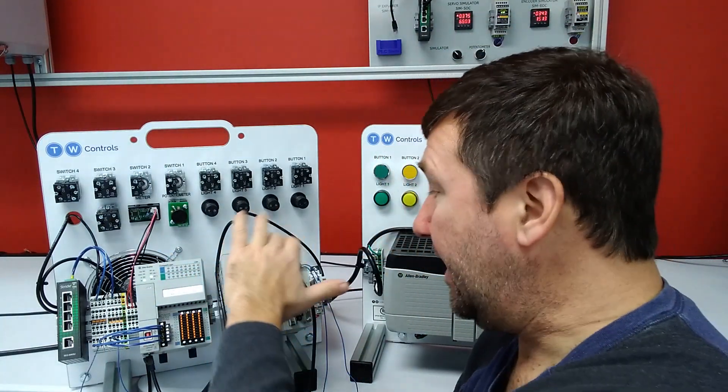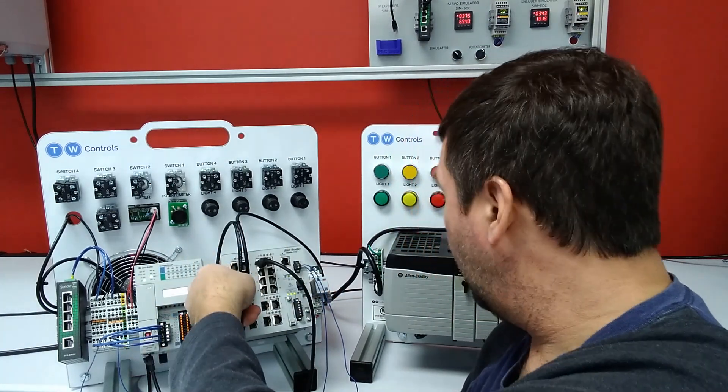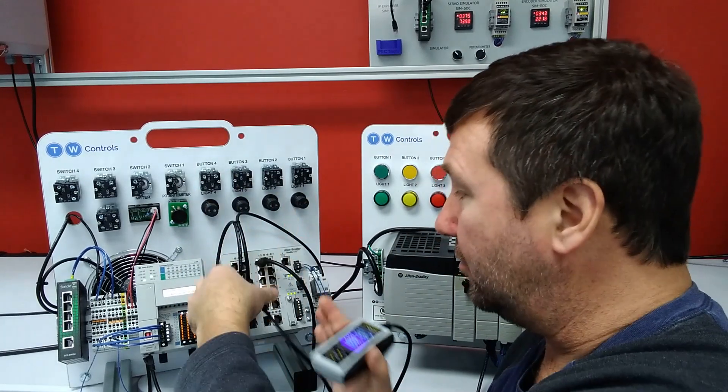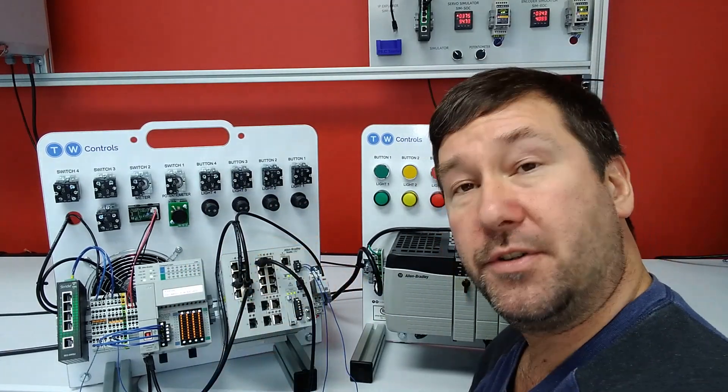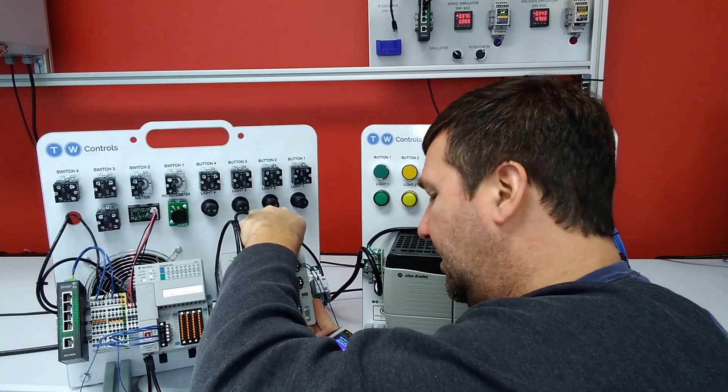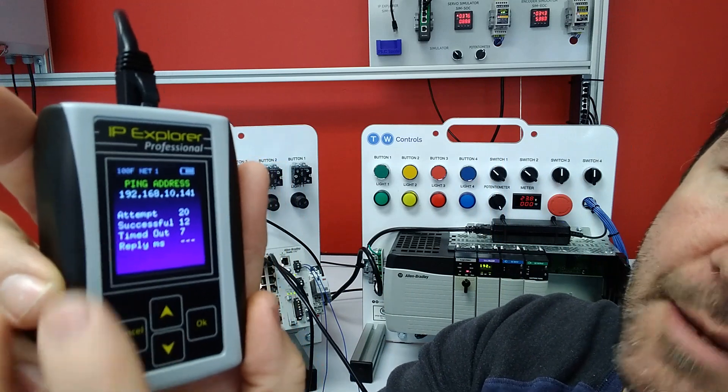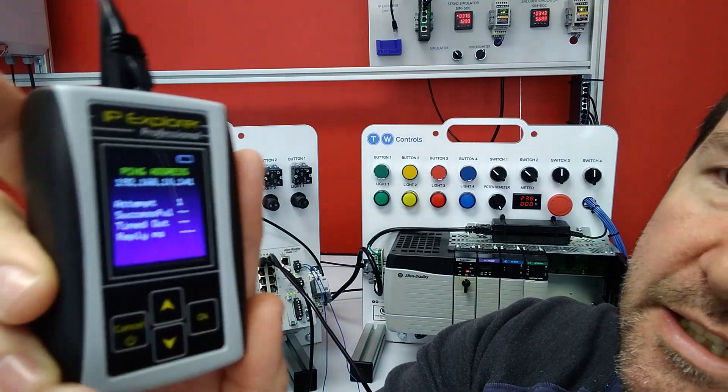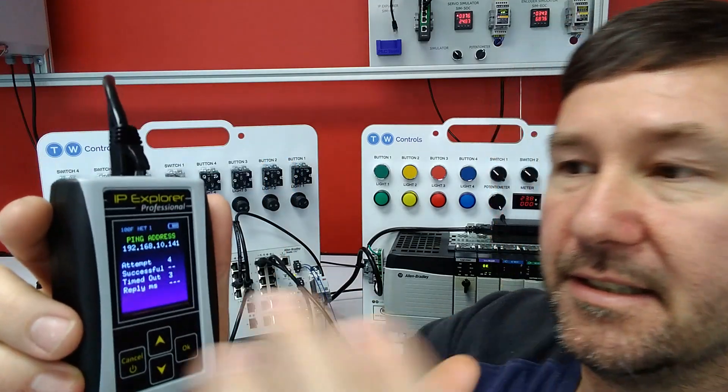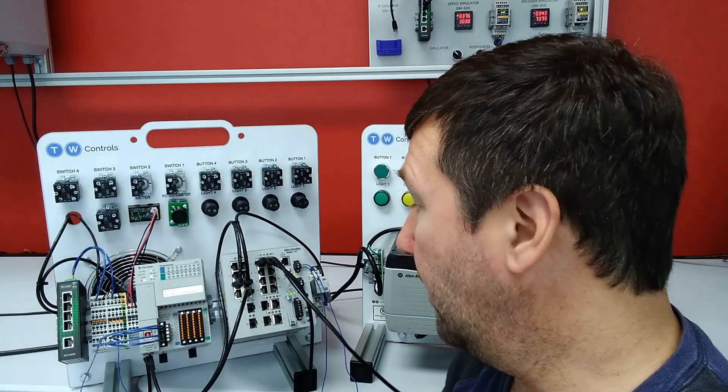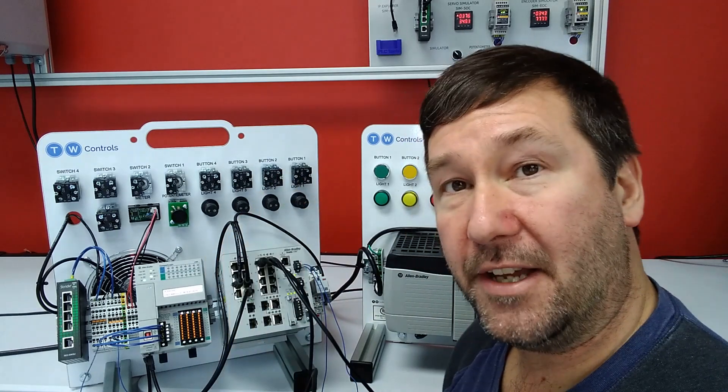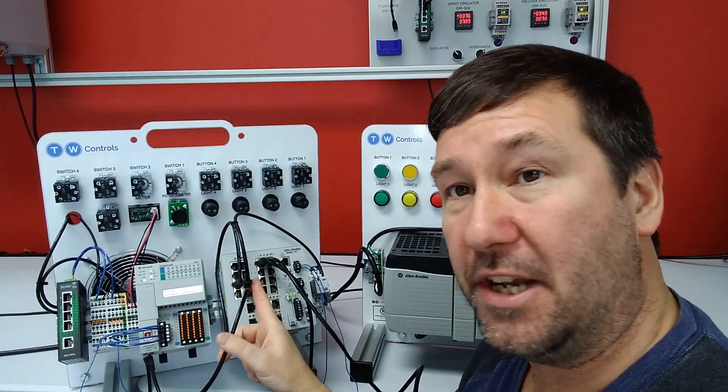But now let's plug into VLAN 20 or mainly what's connected to the control logix. Now we're on the physical same switch. But these four ports are configured so they'll only handle traffic for 192.168.20 IP addresses. So when I plug into it, we're going to continue to get timeouts. In fact, let me cancel and go right back in so that you can see each ping is now failing. And what that is, is so this is looking to go to 192.168.10.141. And this one is not configured to allow that traffic through because this is our 10 network over here.